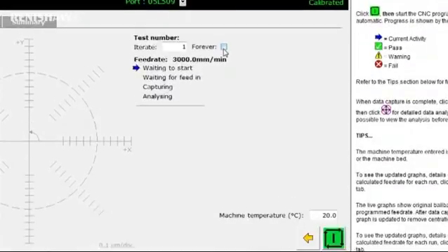As discussed previously, you can enter a temperature for the machine, but it is important that you fully understand the implications of doing so. Applying thermal compensation to the ballbar test will give you an estimate of the results that could be expected if the machine was tested at a nominal 20 degrees Celsius or 68 degrees Fahrenheit. Please refer to the temperature compensation section of the help file for more details.